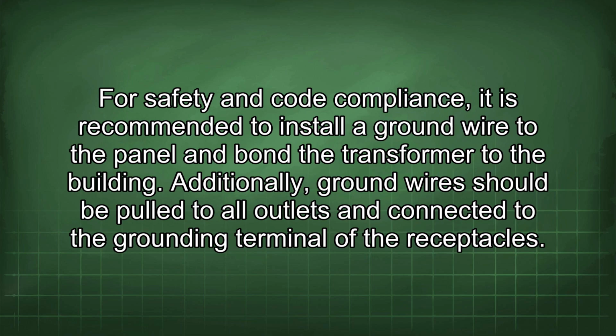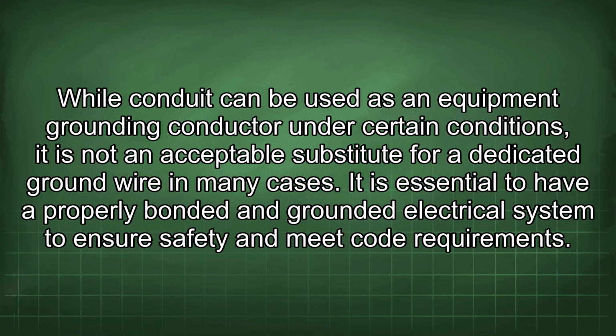For safety and code compliance, it is recommended to install a ground wire to the panel and bond the transformer to the building. Additionally, ground wires should be pulled to all outlets and connected to the grounding terminal of the receptacles. While conduit can be used as an equipment grounding conductor under certain conditions, it is not an acceptable substitute for a dedicated ground wire in many cases. It is essential to have a properly bonded and grounded electrical system to ensure safety and meet code requirements.